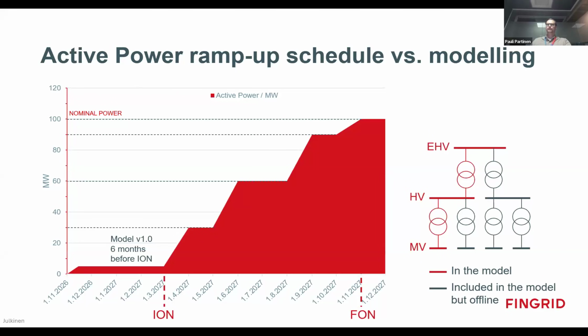Then one of the issues in the data center model delivery is the ramp-up phase of the plant: what should be modeled in the first phase, and how the models develop for the ramp-up period. Here is our solution to the problem. The first model of the plant shall be delivered to us 6 months prior to the interim operational notice, ION, which means that after that, the demand plant can start the normal consumption. The model goes through a model validation, where we check that everything is correctly modeled. In the first model, the full demand plant up to the nominal power shall be modeled, but only the first block shall be online, basically.